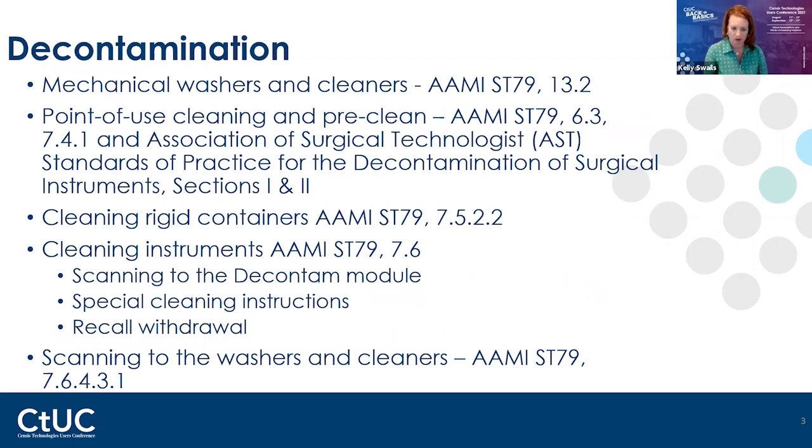So decontam, good old decontam. Right off, AAMI ST79 clearly states that mechanical cleaning equipment should be tested each day that it is used. And it should be documented with the name, date, and time of who is performing that task. One thing that speaks volumes to me is that it should be tested each day that it's used. So if you don't staff on the weekends or holidays, you don't have to worry about it, unless they come in for an add-on case, then that would be one thing.